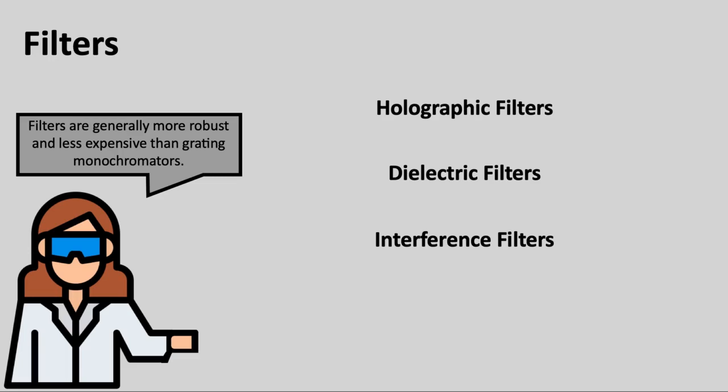But in all cases, filters basically permit certain bands of wavelengths to pass through them while either absorbing or reflecting other wavelengths. Filters are, in general, more robust and less expensive than grating monochromators, but they often have lower resolution when compared to monochromators, so there's a definite trade-off.